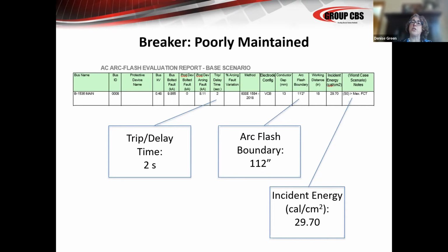So your technician or electrician that's standing in front of that gear, anticipating a 2-calorie event if something happens, is now standing in front of an almost 30-calorie event wearing 8-calorie PPE. So that is why it's super important to understand that a lack of maintenance directly impacts arc flash situations. Now we have crossed the line. If there is an arc flash, it's no longer a 2-calorie arc flash. It's a 30-calorie arc flash. We've crossed the line into equipment failure, debris, slinging bolts, doors flying open, all of those things happening, and no one anticipated it because they went by the label.